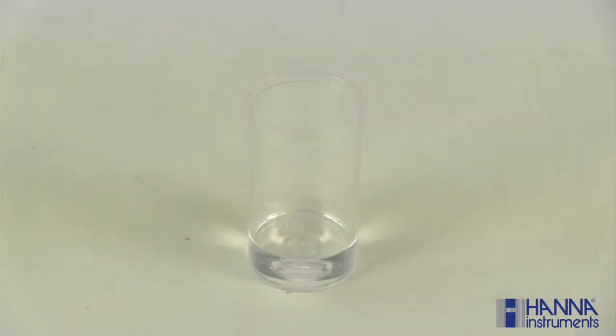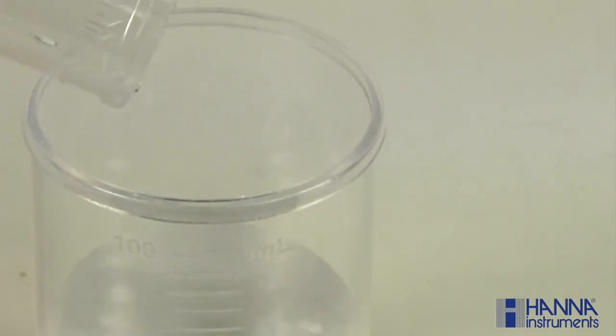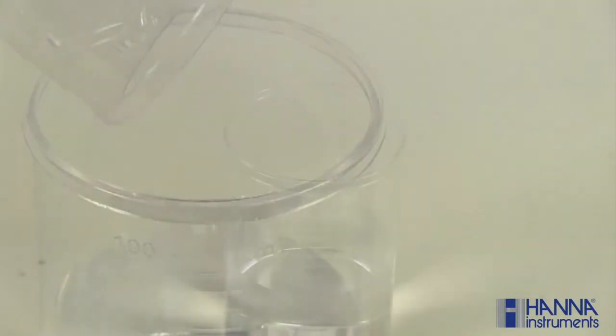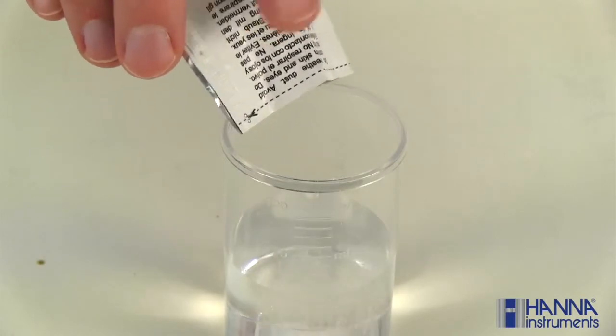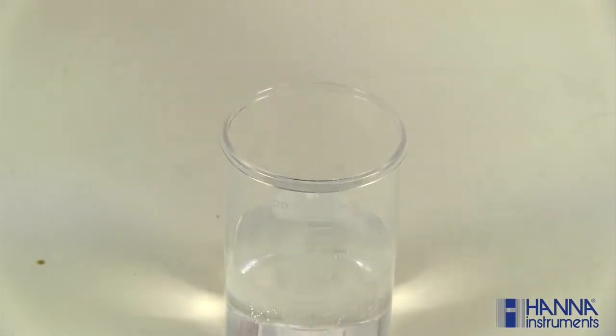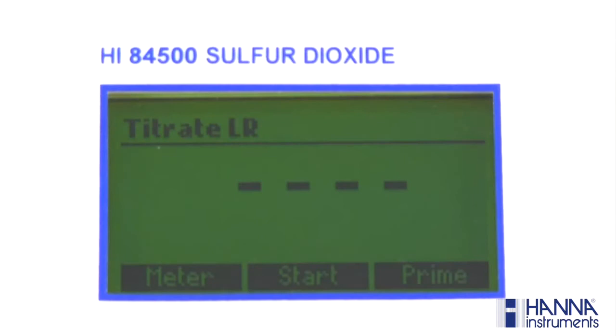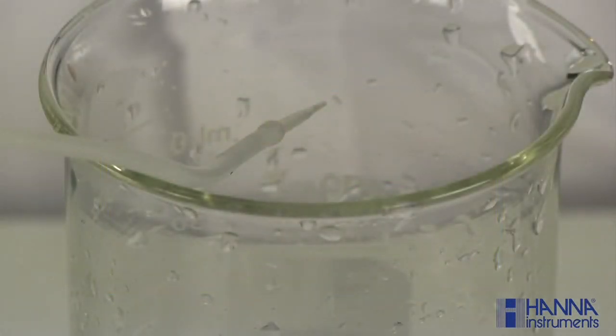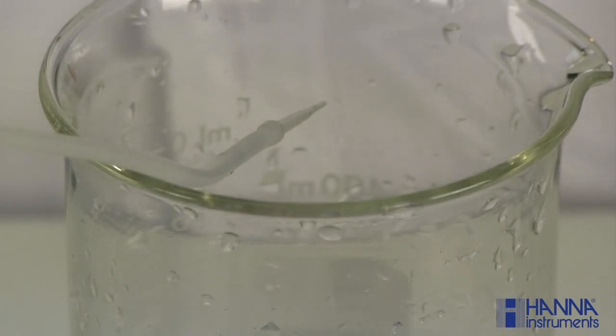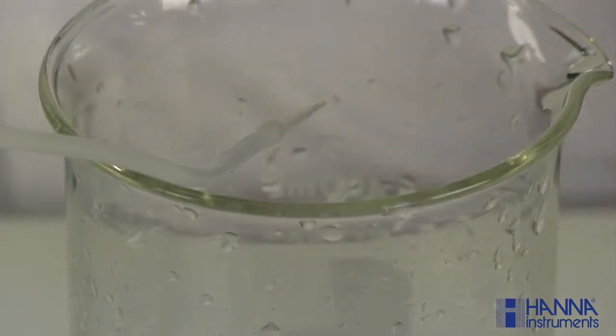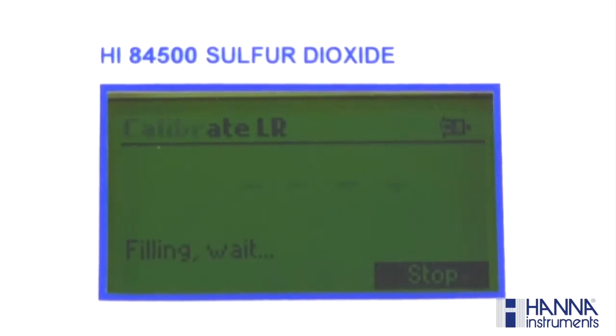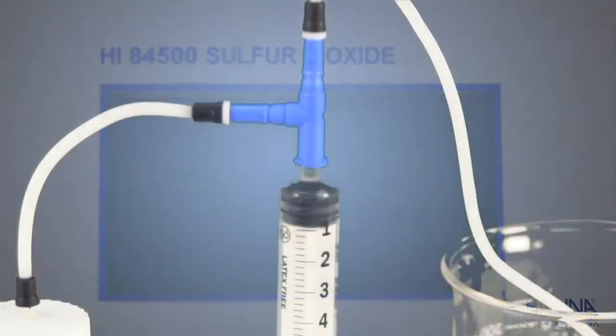Next, fill the 20 milliliter beaker up to the 5 milliliter mark with HI-84500-60 acid reagent and add it to the 100 milliliter beaker. Add the contents of 1 packet of HI-84500-62 stabilizer packet to the 100 milliliter beaker. Press the Cal key. Place the dosing tip over a waste beaker. This is important. A small amount of titrant is dispensed when the pump resets. Press Start and wait for the syringe to refill.